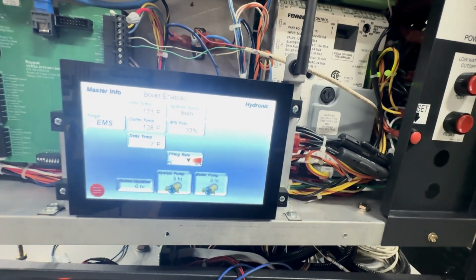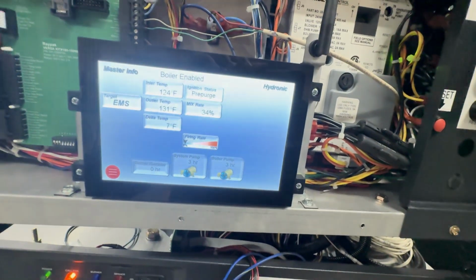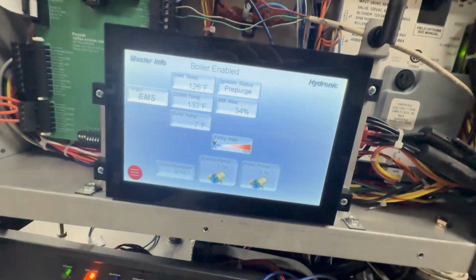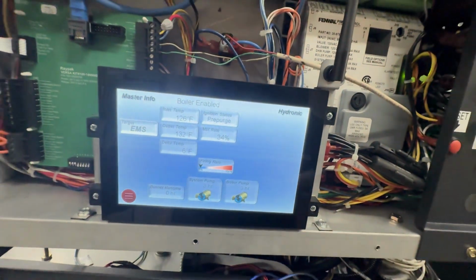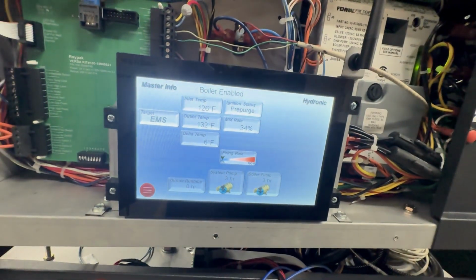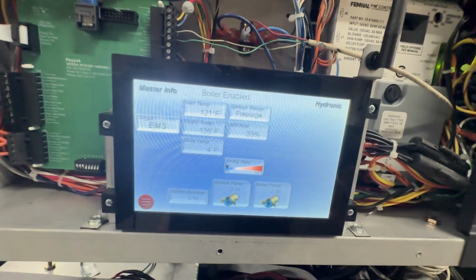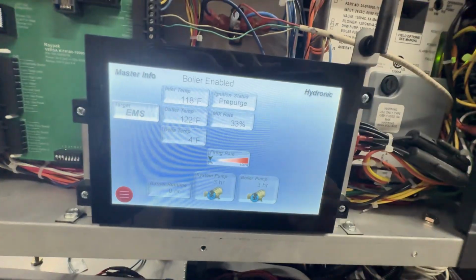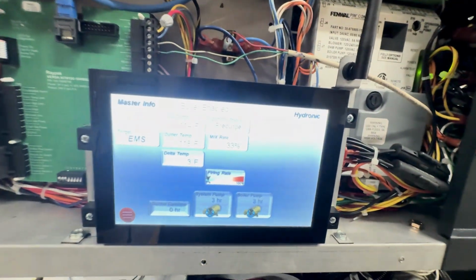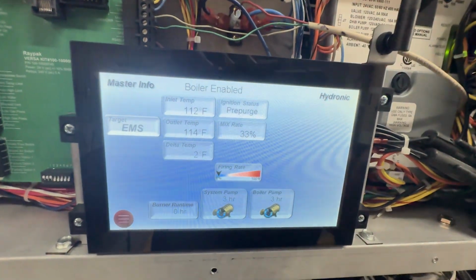And there, the boiler just tripped. Pre-purge. And it's off. So typically the way these boilers work is they're gonna try to ignite 3 times. After the 3rd time, it'll go into a soft lock. You're gonna have to reset it right here, but for our intents and purposes, this worked just fine.